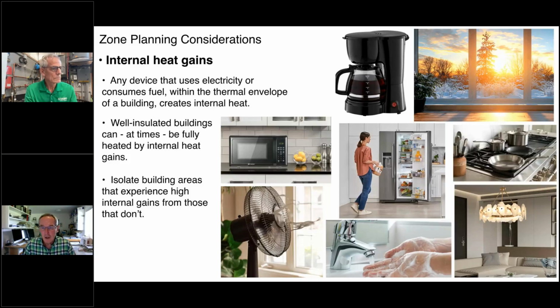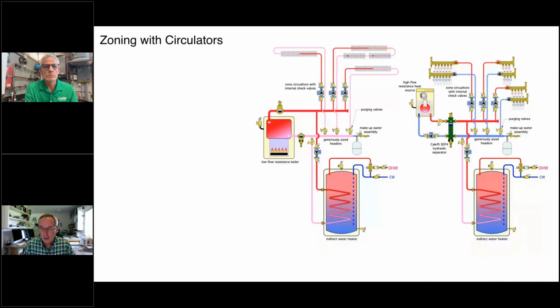Okay, now we're going to talk first about zoning with circulators. And these are a couple graphics that will be in Hydronics 36. The first one here on the left, that's a very common residential system. We've got 3 zones of fin tube baseboard, each with their own circulator. And if you look carefully at the circulators, you see that little Z shape. That means there's an internal check valve. Having a check valve, whether it's internal to the circulator or external, is extremely important. We're going to talk about it in more detail.